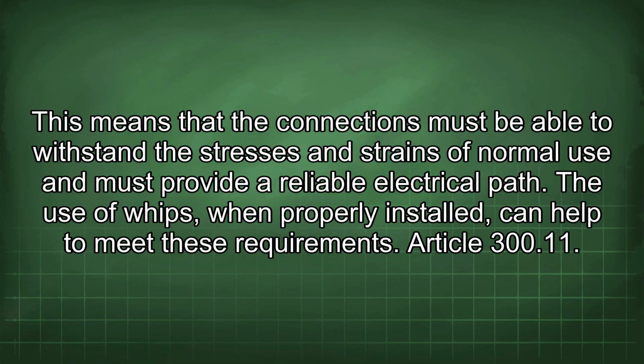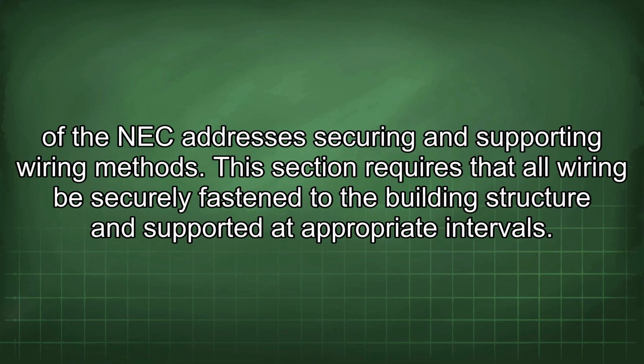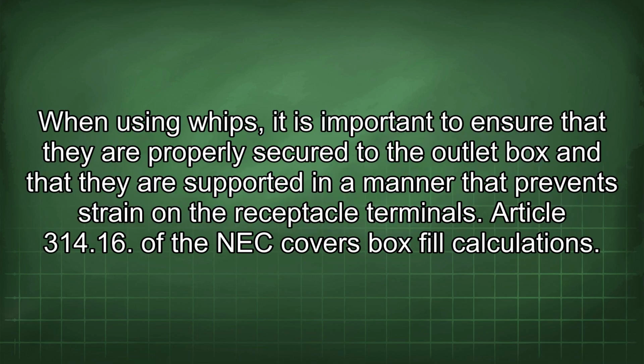Article 300.11 of the NEC addresses securing and supporting wiring methods. This section requires that all wiring be securely fastened to a building structure and supported at appropriate intervals. When using whips, it is important to ensure that they are properly secured to the outlet box and that they are supported in a manner that prevents strain on the receptacle terminals.